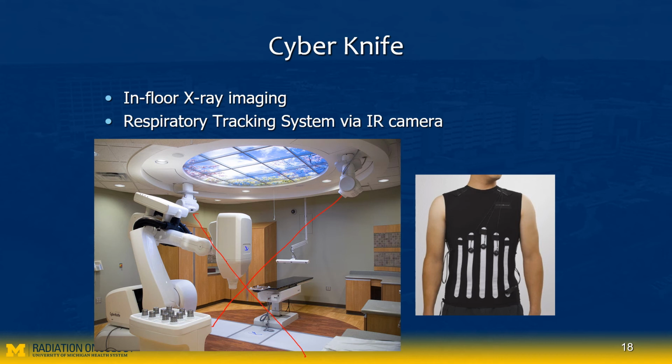Yeah. So the disadvantage of this system is it's not a volumetric acquisition, right? It's only 2D snapshots. But it can be acquired in a very short period of time, so it can be used multiple times throughout the treatment to verify patient position or tumor location.